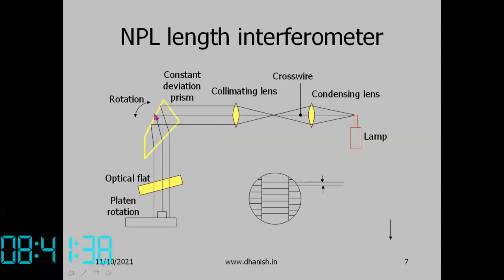One colour — monochromatic light — is made to pass through the optical flat. There is a platen which can be rotated, over which the gauge block is placed. Light falling on the flat platen is reflected back, and light falling on the top surface of the gauge block is also reflected back. Between the two there is a height difference resulting in a path difference, so there will be interference fringes and a shift of these fringes. What we actually measure is the fractional shift of the interference fringes.